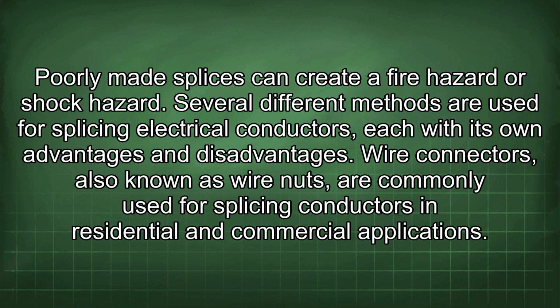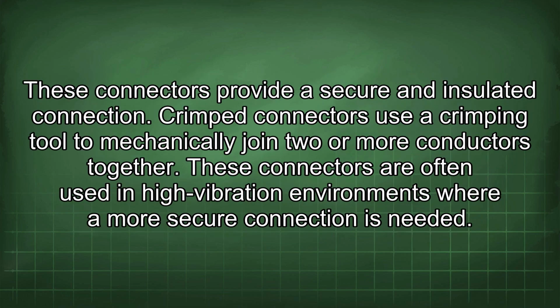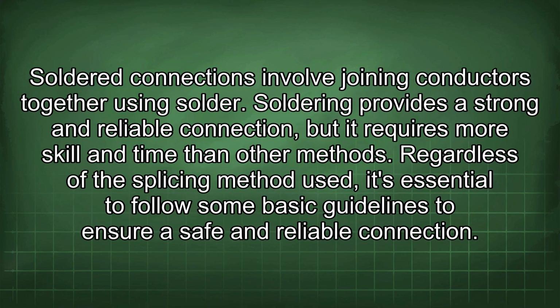Several different methods are used for splicing electrical conductors, each with its own advantages and disadvantages. Wire connectors, also known as wire nuts, are commonly used for splicing conductors in residential and commercial applications. These connectors provide a secure and insulated connection. Crimped connectors use a crimping tool to mechanically join two or more conductors together. These connectors are often used in high vibration environments where a more secure connection is needed. Soldered connections involve joining conductors together using solder. Soldering provides a strong and reliable connection, but it requires more skill and time than other methods.